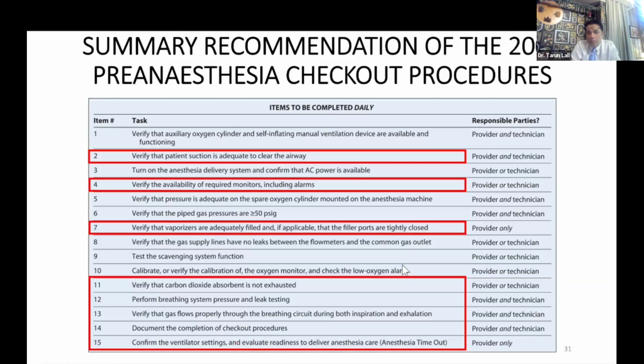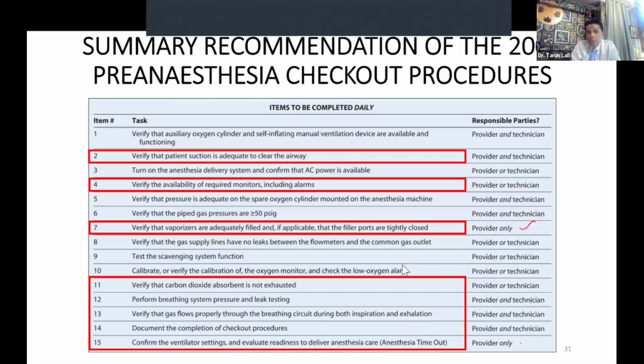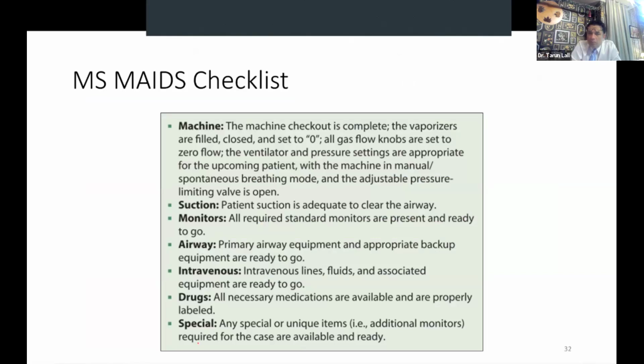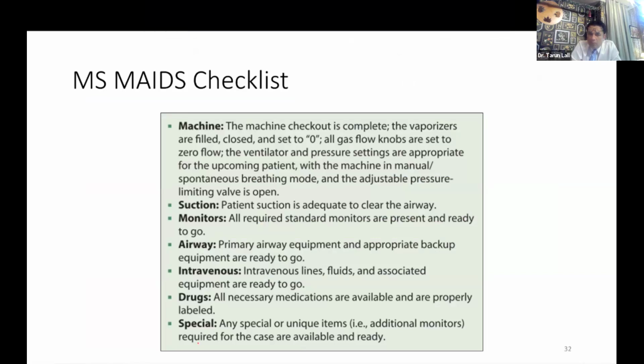Another important thing is that there are 2 tests which you mandatorily have to do yourself. Some tests are provider and technician, some tests are provider or technician. So there are 2 tests which have to be done by the anesthetist only. One is whether your vaporizers are correctly filled or not, and second is to confirm the ventilator settings and evaluate readiness to deliver anesthesia. That is what we call the anesthesia timeout. During the anesthesia timeout, Miller recommends the MS MAIDS checklist. You will have your own checklist. SOAP ME, I have heard many of you use. Whichever checklist you use in your OT, do it. But the anesthesia timeout must be done by the anesthesia provider and not by the technician.